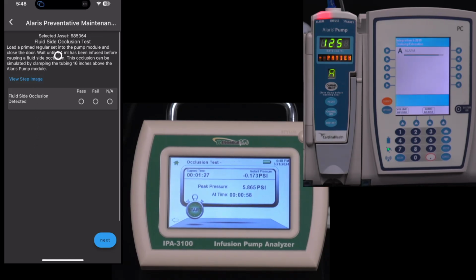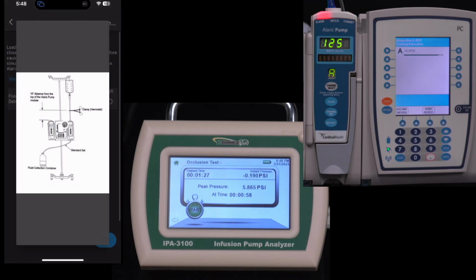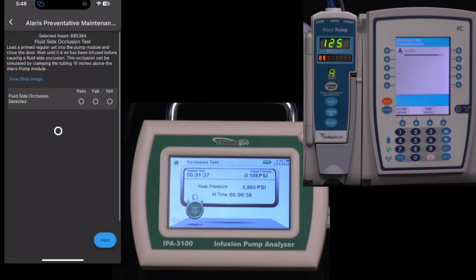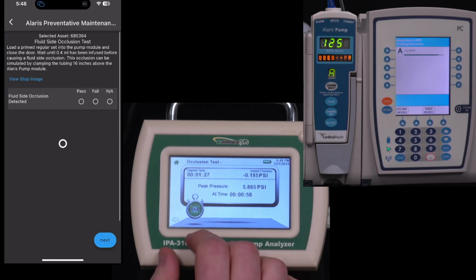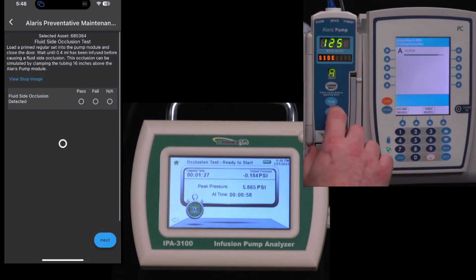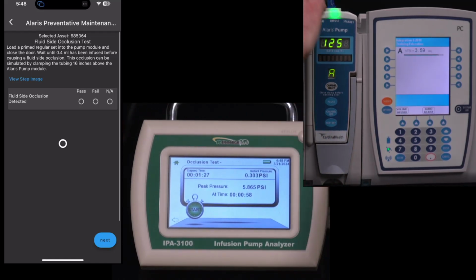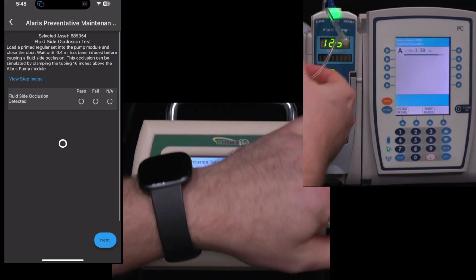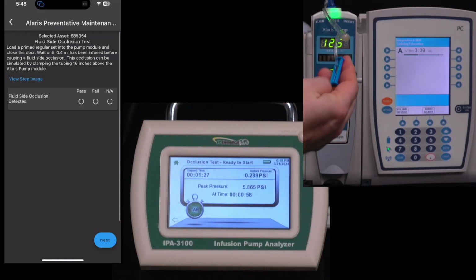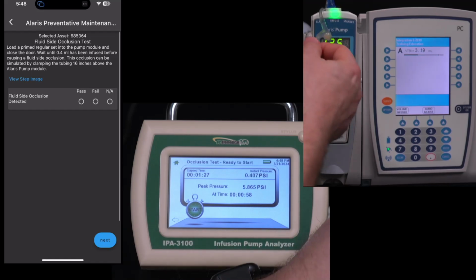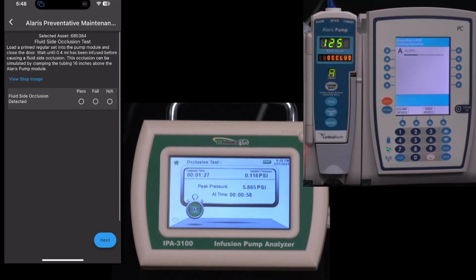So then we're going to do a fluid side occlusion, and we can look at the test picture. It says occlude between the fluid source and the pump. So we'll go ahead and do that. Now I'm going to restart the pump so that it's flowing. And then I have a little clamp. Let's see if I can get this in the camera. Yep, I've got a little clamp here on the inlet side. I'll go ahead and occlude that. And it detected that right away. So that's a pass for that. I'll go ahead and clear that.